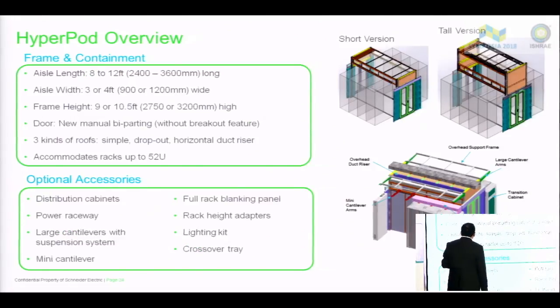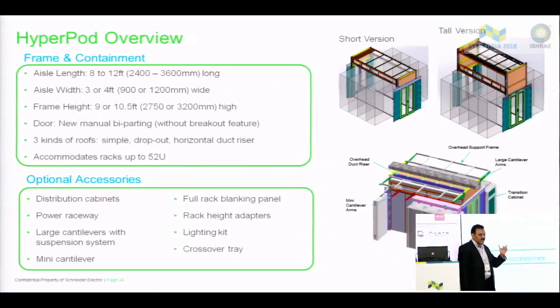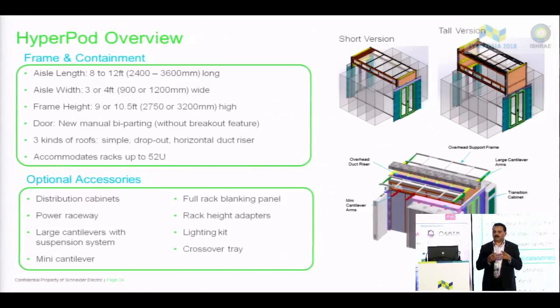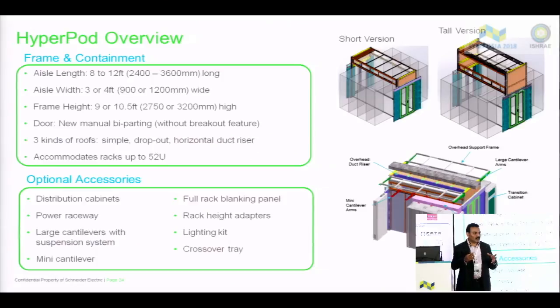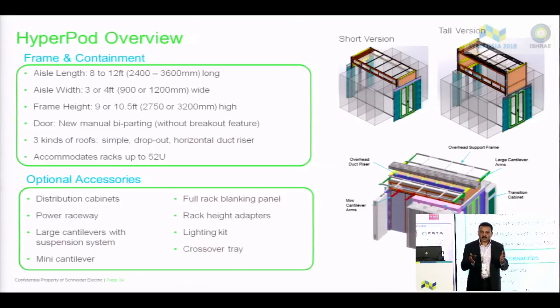In summary, for a single pod, which is available, you can vary from 8 to 12 feet. It can vary. The aisle can vary between 3 to 4 feet. Continuously, it can be varied.